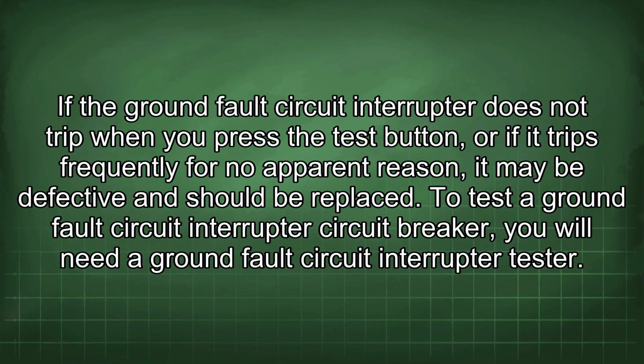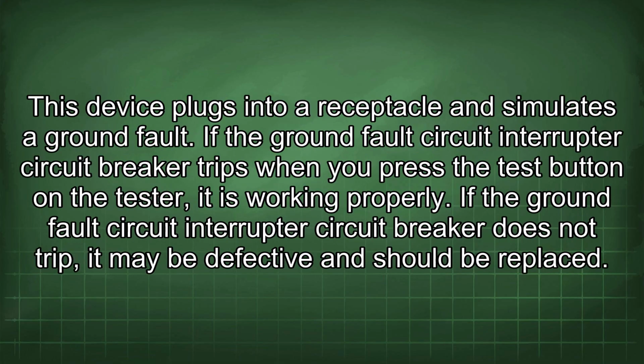If the ground fault circuit interrupter does not trip when you press the test button, or if it trips frequently for no apparent reason, it may be defective and should be replaced. To test a ground fault circuit interrupter circuit breaker, you will need a ground fault circuit interrupter tester. This device plugs into a receptacle and simulates a ground fault. If the ground fault circuit interrupter circuit breaker trips when you press the test button on the tester, it is working properly.